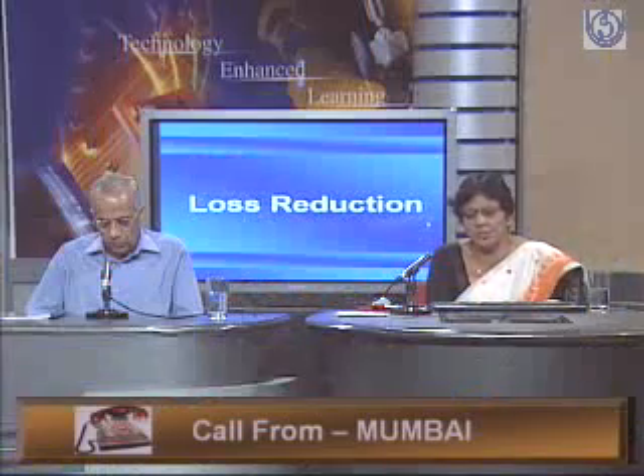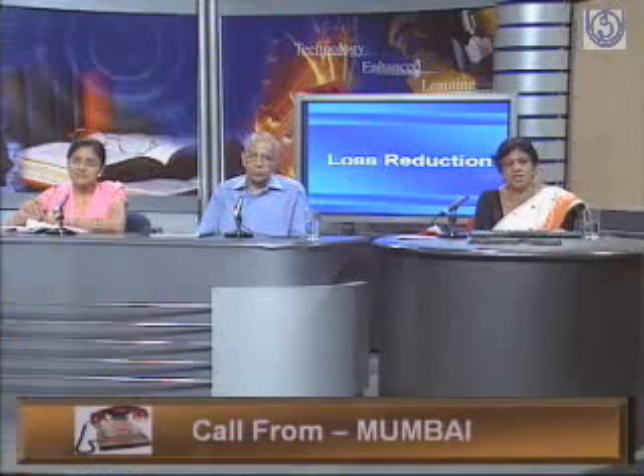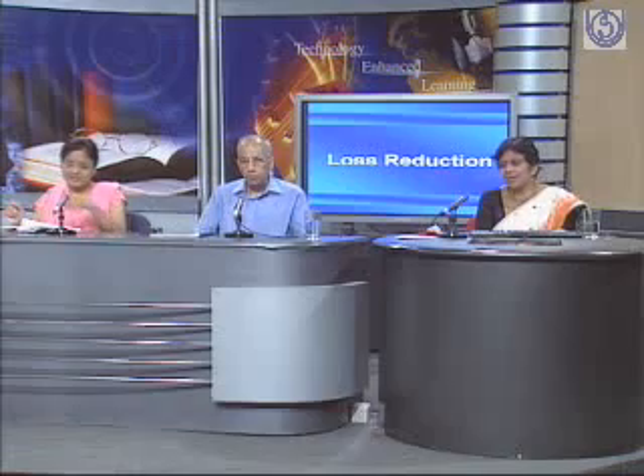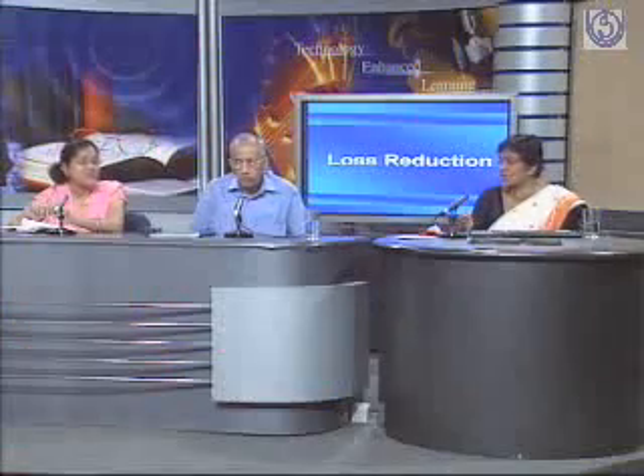I don't think there is any proposal to bring down the voltage at the consumer end from 230 to 110 volts, because as we talked, the higher voltage you go to, the losses will be less. But at the consumer end, if you are to have a 110 volt system, then your LT lines have also to be 110. And the current in the LT lines will be much higher, corresponding to 110 volt as compared to 230 volt. So it will not bring down losses, it will increase the losses if you go down to 110 volt at the consumer end. All the appliances have to be designed on the same rating. No, everything will have to be designed, but even if you do bring it, your losses are going to increase, not decrease.